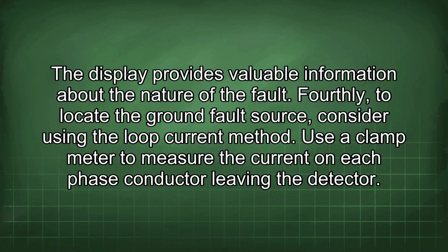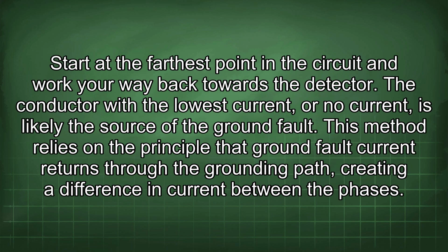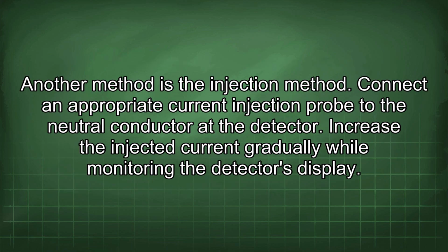Fourthly, to locate the ground fault source, consider using the loop current method. Use a clamp meter to measure the current on each phase conductor leaving the detector. Start at the farthest point in the circuit to work your way back towards the detector. The conductor with the lowest current, or no current, is likely the source of the ground fault. This method relies on the principle that ground fault current returns through the grounding path, creating a difference in current between the phases. Another method is the injection method.